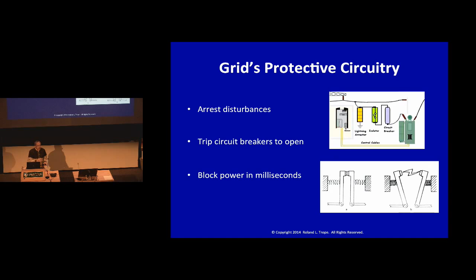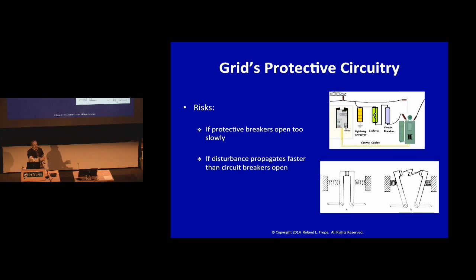The risks are that if the breaker doesn't open fast enough, if it opens slowly or if it opens out of phase, the disturbance will get through before that happens. And if it gets to equipment like transformers and generators that are not designed to cope with that strong a disturbance or for that duration, you're going to have a problem. The problem will, as likely as not, knock that unit offline, or worse, it could cause it to self-destruct, possibly resulting in a devastating fire.